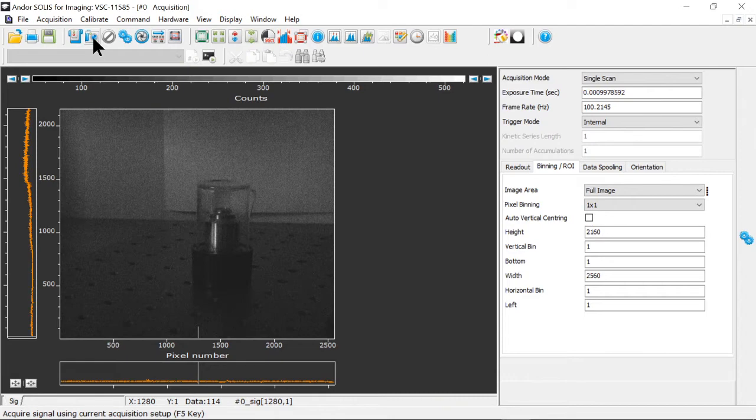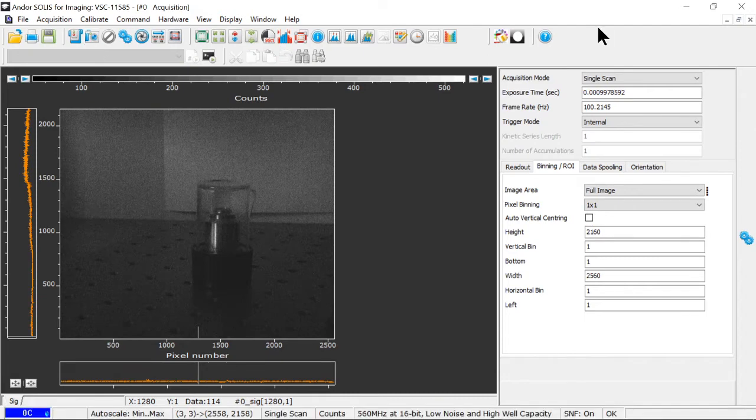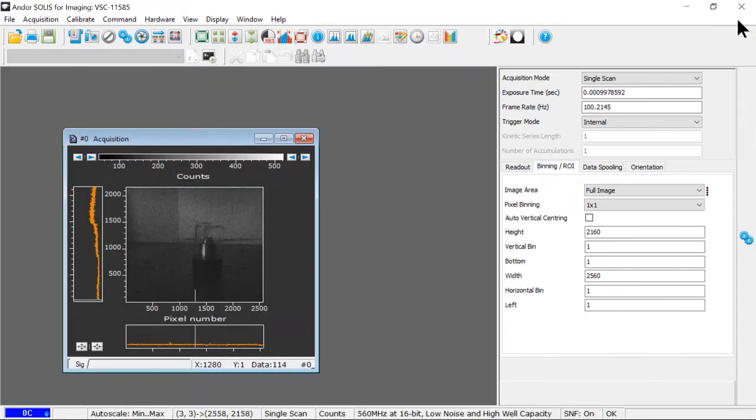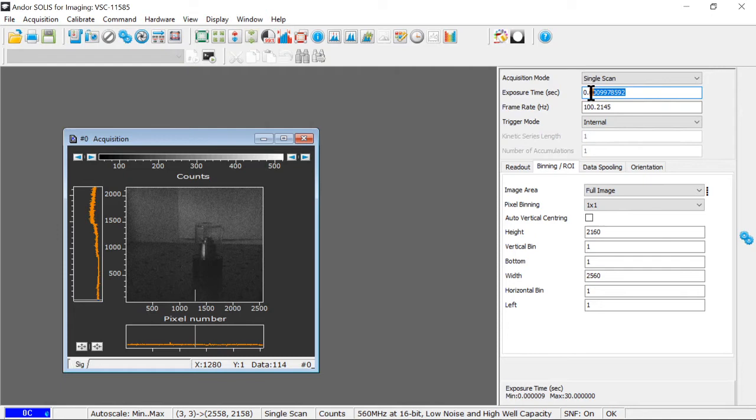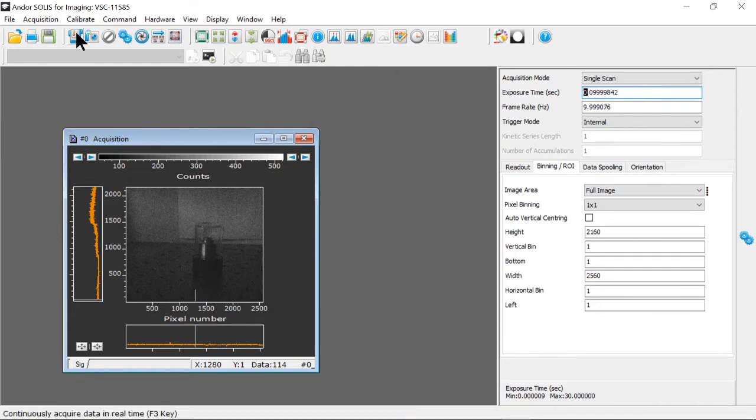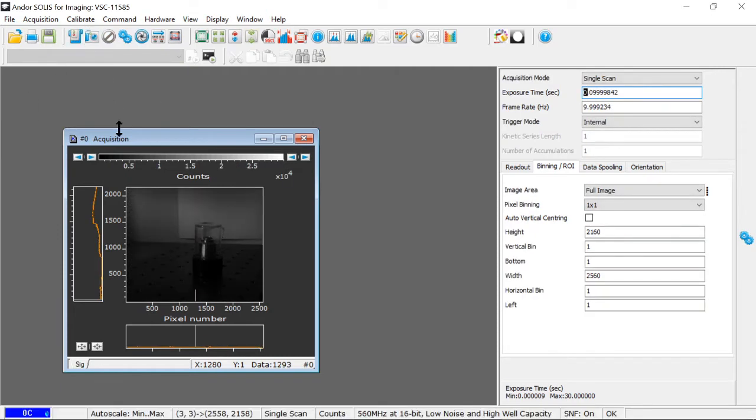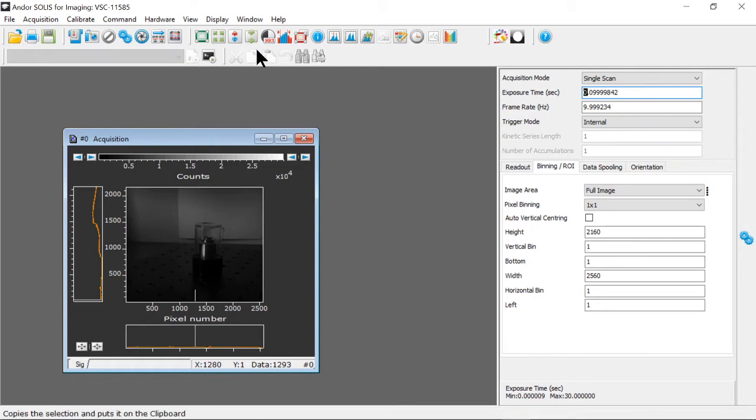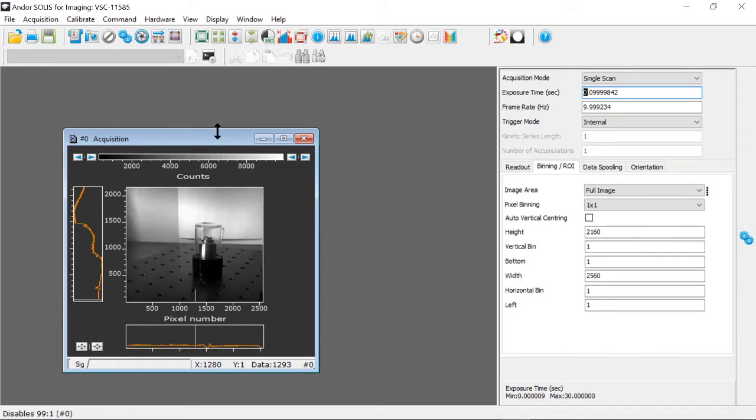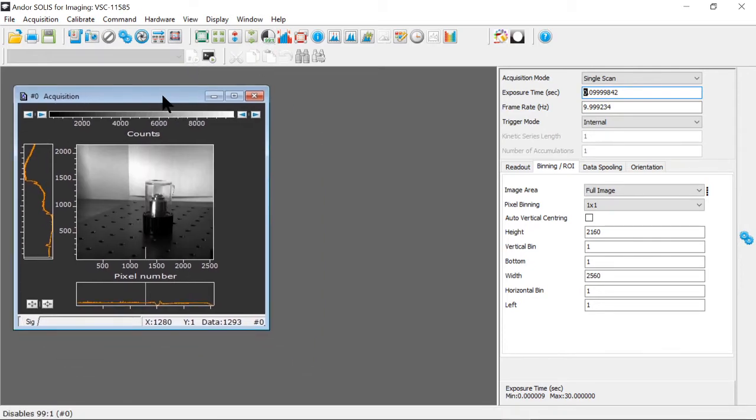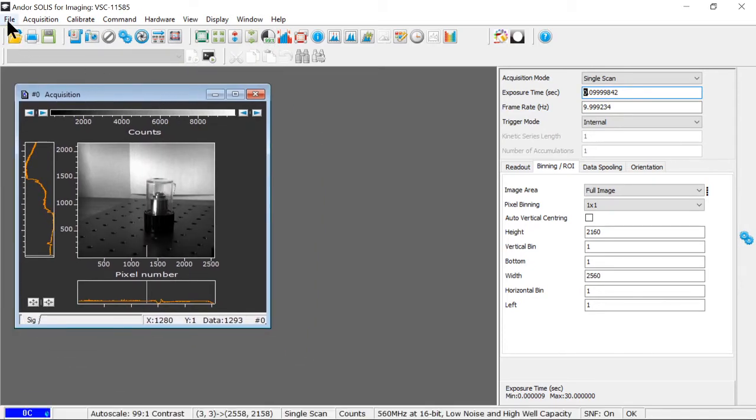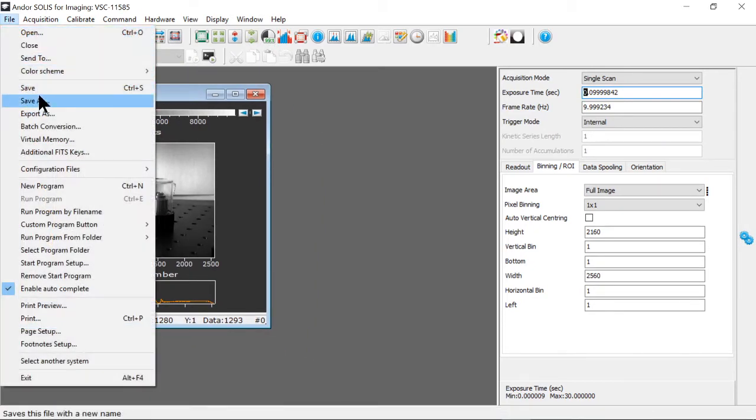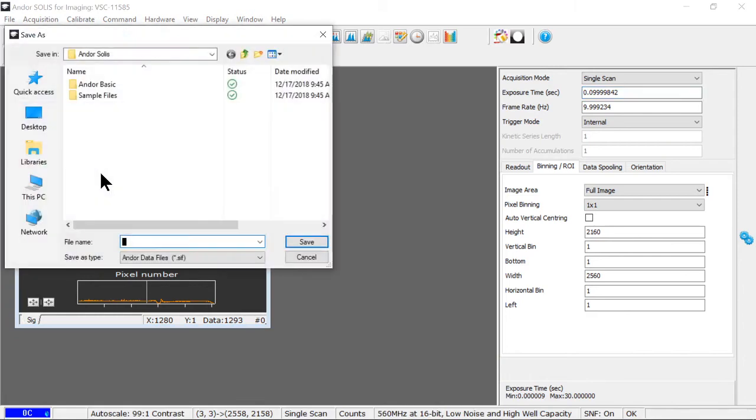To get more counts and increase my signal-to-noise ratio, I can do one of two things right now. I can take a longer exposure or I can accumulate multiple exposures. So say I want to collect 100 times as much signal here. I could go to 100 milliseconds from one millisecond and I'll do a single exposure with a longer exposure time now. So you can see the signal-to-noise ratio has gotten quite a bit better. I'm going to save this so we can compare it.